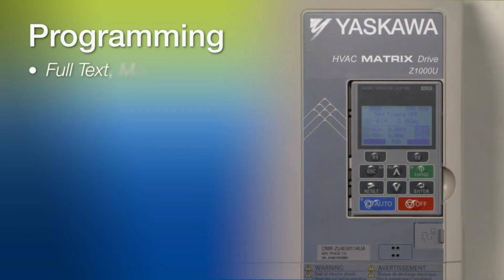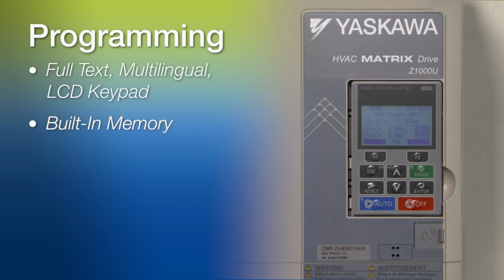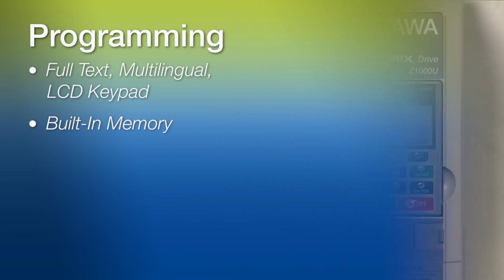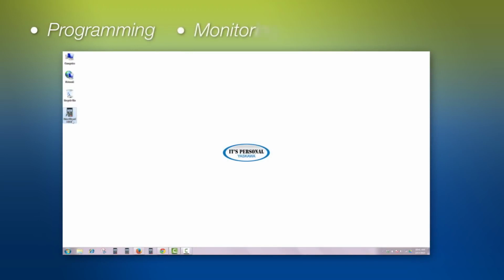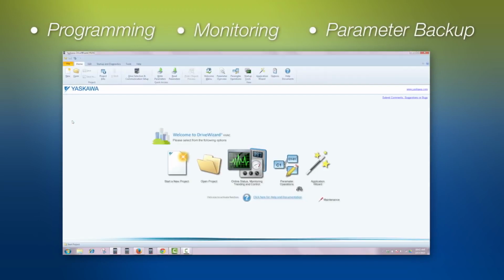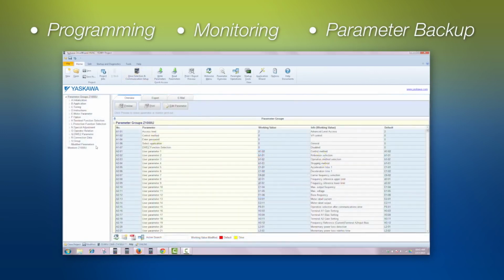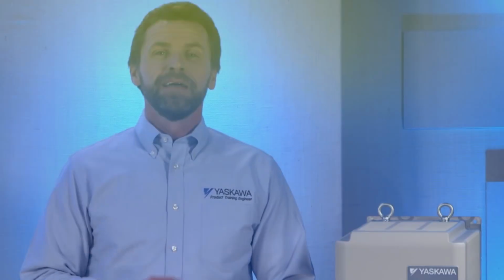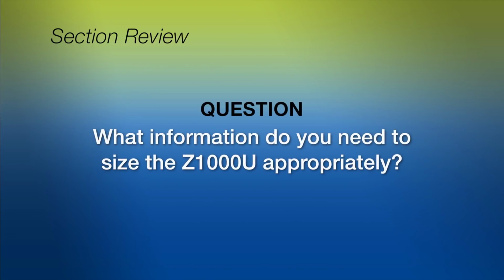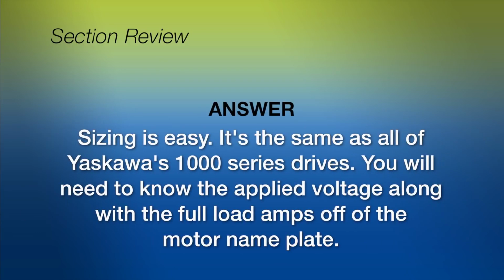Programming can be done through the full-text multilingual LCD keypad. This keypad also has built-in memory, making it possible to back up your parameter settings. Programming, monitoring, and parameter backup can also be accomplished using Yaskawa's free DriveWizard HVAC support tool. And now we have one last question for you. What information do you need to size the Z1000U appropriately? And the final answer is, sizing is easy. It's the same as all of Yaskawa's 1000 series drives. You will need to know the applied voltage along with the full load amps off of the motor nameplate.